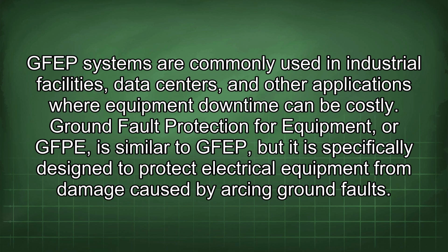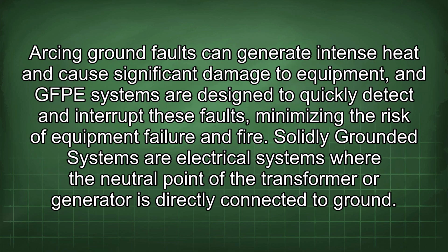Ground fault protection for equipment, or GFPE, is similar to GFEP, but it is specifically designed to protect electrical equipment from damage caused by arcing ground faults. Arcing ground faults can generate intense heat and cause significant damage to equipment, and GFPE systems are designed to quickly detect and interrupt these faults, minimizing the risk of equipment failure and fire.